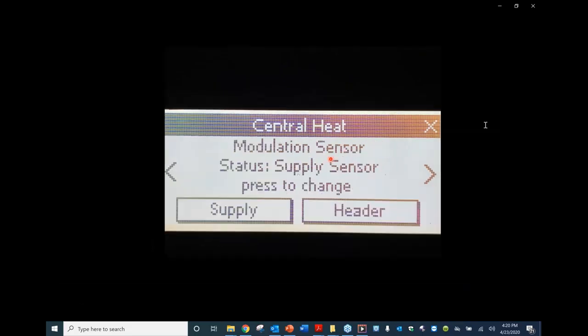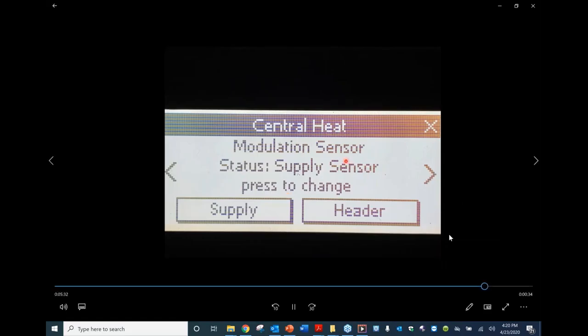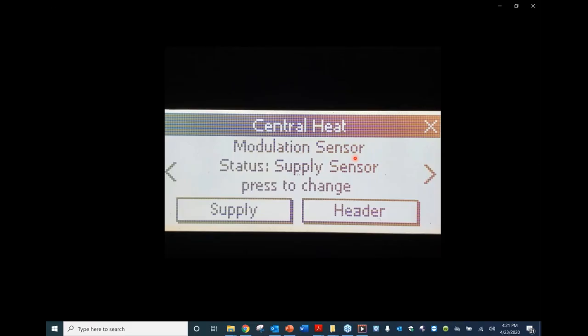The last menu in here is going to be our modulation sensor. Out of the box, it's going to be looking for the supply sensor. There is an optional header sensor that can be installed on the boiler where it would monitor the header temperature and it would modulate off of the header temperature. If you're doing multiple boilers, and that would be covered in another video, the header sensor is required.